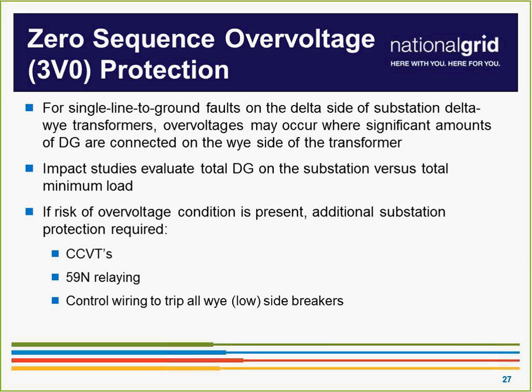If you guys want more detail later on, I can explain directly. Due to the nature of the transformer, there's overvoltage on the transmission side. In our studies, the approach we use to evaluate these projects is comparing the minimum load of that substation against the added DG production at the substation. We do the evaluation by comparing both.